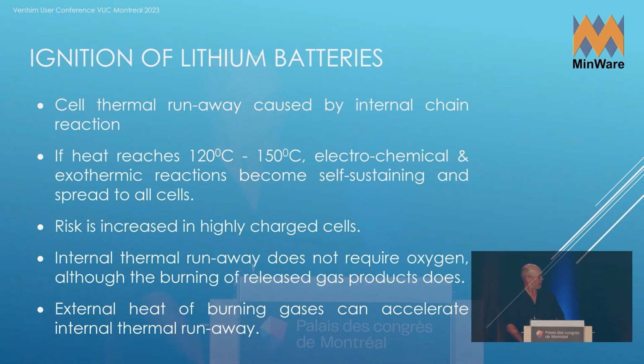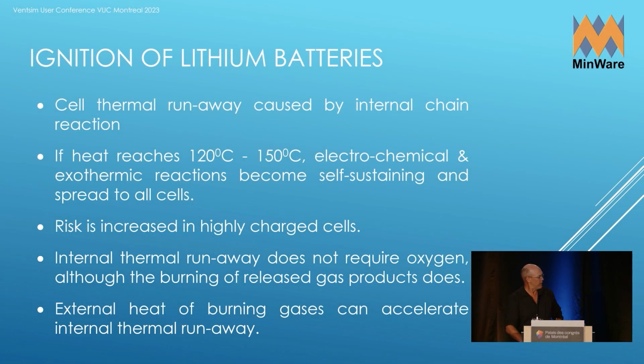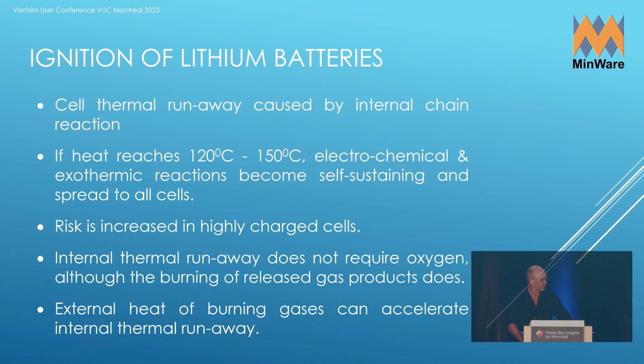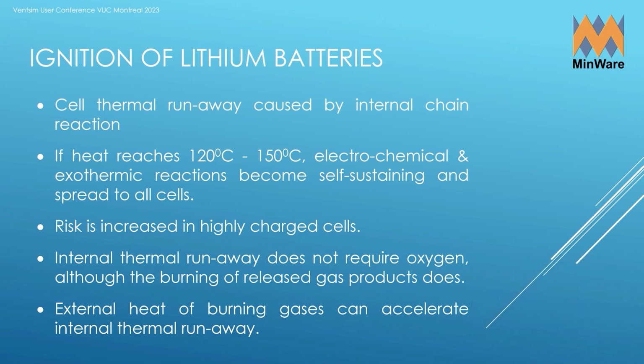Once that thermal runaway occurs, at about 120 to 150 degrees, off she goes - it's like a chain reaction. The only way to stop that from propagating is to cool the battery, typically by putting lots of cool water on it, or immersing it if possible. But if you don't do that, the thermal runaway continues until the battery catches fire and the whole thing burns to the ground.